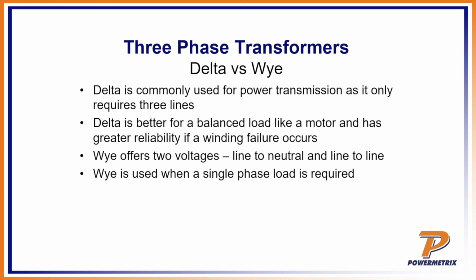And the Y offers 2 voltages, line to neutral and line to line, and the Y is used when a single phase load is required. So what we're saying there is, looking at the delta, if you lose a leg, you would still have phase to phase, right? But if you lose a leg on a Y, then you're done. So that's one consideration of why people would go delta. And then the other is the cost, right? That's one less conductor you have to run. So it's both cost, and in those situations where you might lose a leg, which happens with motors and stuff, then you won't be dead, okay?